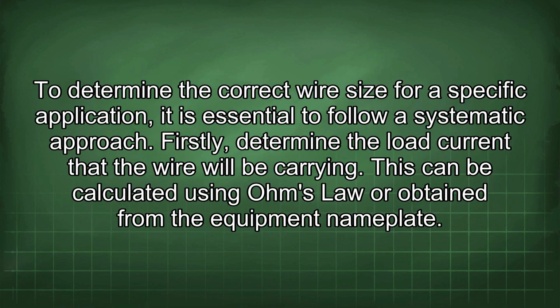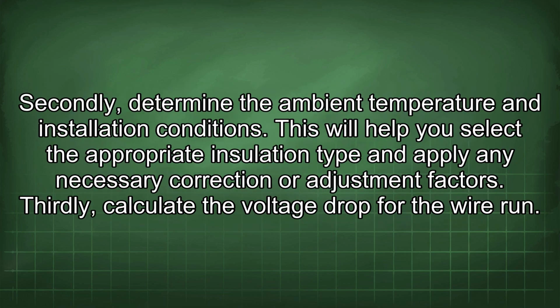To determine the correct wire size for a specific application, it is essential to follow a systematic approach. Firstly, determine the load current that the wire will be carrying. This can be calculated using Ohm's law or obtained from the equipment nameplate. Secondly, determine the ambient temperature and installation conditions.